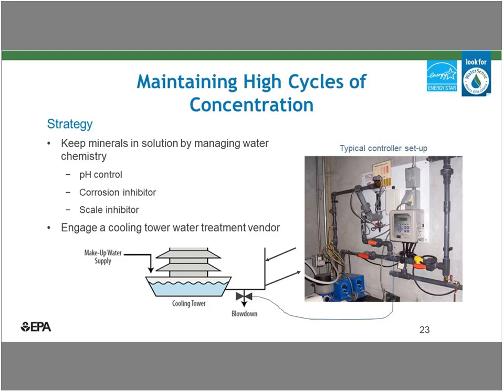So that background establishes the basis for saying that as you maximize your cycles of concentration and reduce blowdown, your system's efficiency will improve. To maintain high cycles of concentration, you'll want to keep minerals in solution by managing the system's water chemistry. Minerals are kept in solution by adding chemicals that can control the pH, inhibit scale, or inhibit corrosion. We encourage you to work with a water treatment vendor, and we have one as a case study today that shares your goals to achieve water efficiency. Working together, you can establish targets for your cycles of concentration based on your local water chemistry and water treatment options.